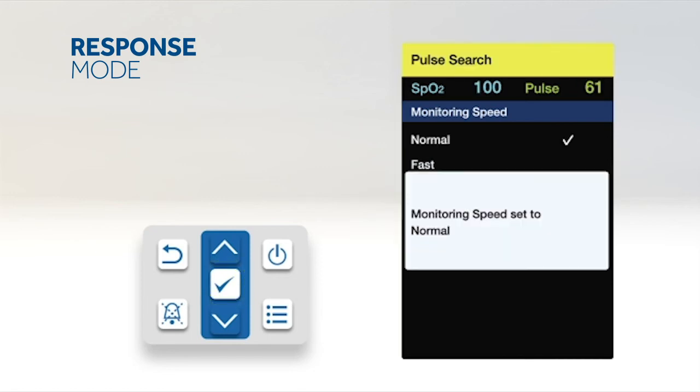When set to normal, changes in blood oxygen saturation are reported within five to seven seconds. When set to fast, changes in blood oxygen saturation are reported within two to four seconds.